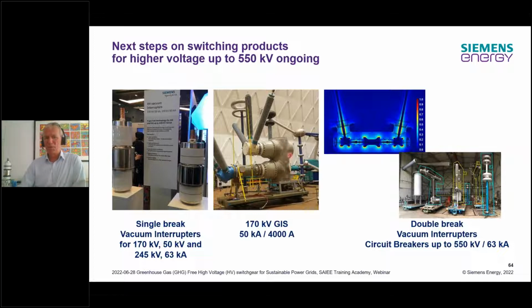In the middle you see the 170 kV GIS for 50 kA, a special Korean design. On the upper right-hand side is a simulation view of a dead tank breaker with two vacuum interrupter units for 550 kV. On the lower right-hand side, you see our test fields where we do the first testing on double breaking - we take the 245 kV vacuum interrupter, put them in series as a double break, and realize circuit breakers up to 550 kV and 63 kA. That's the way forward.